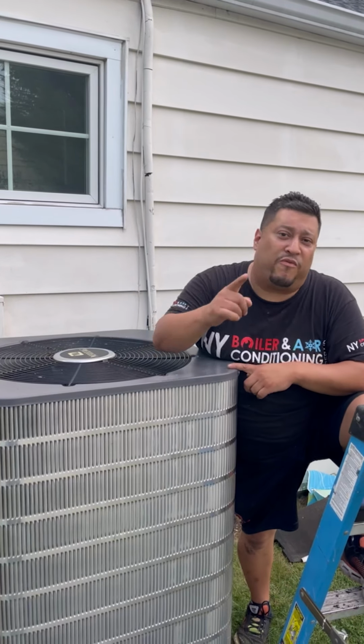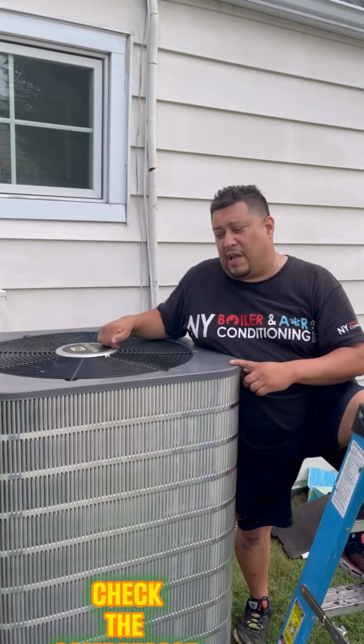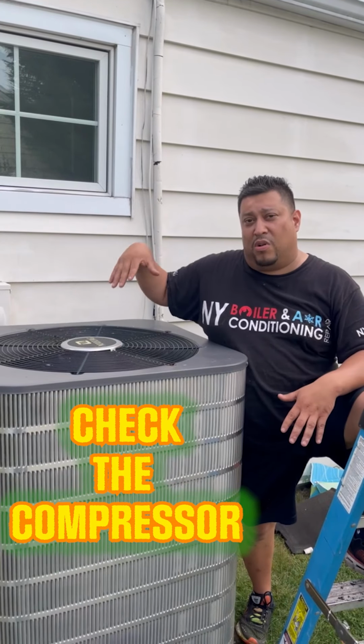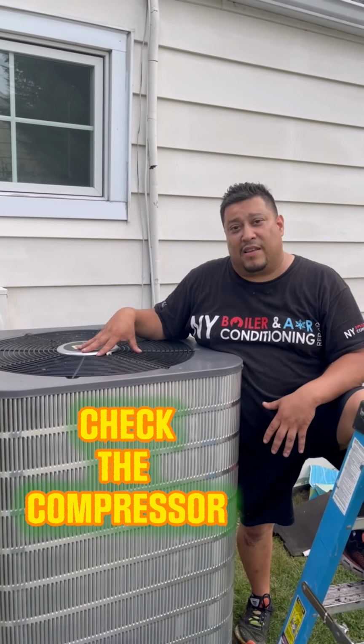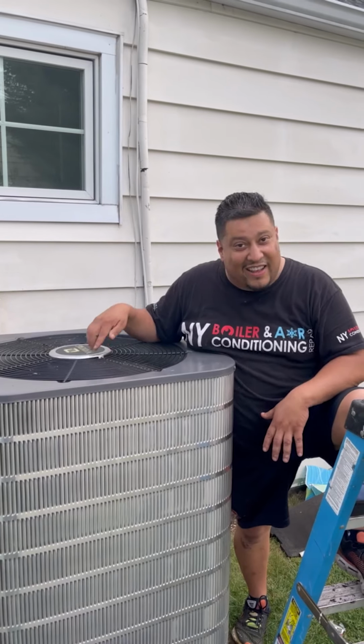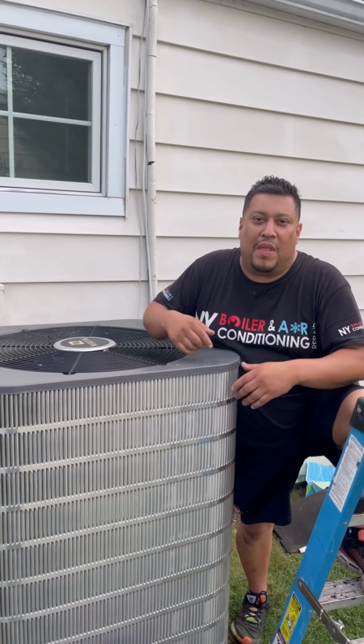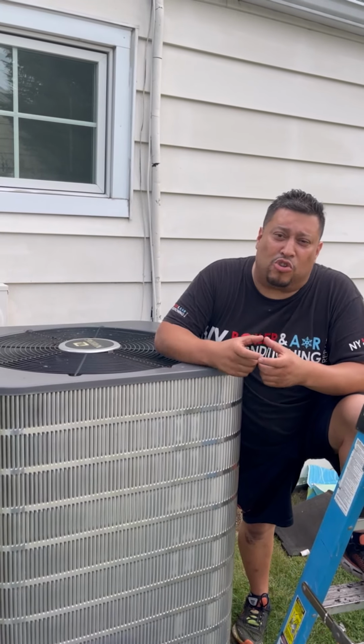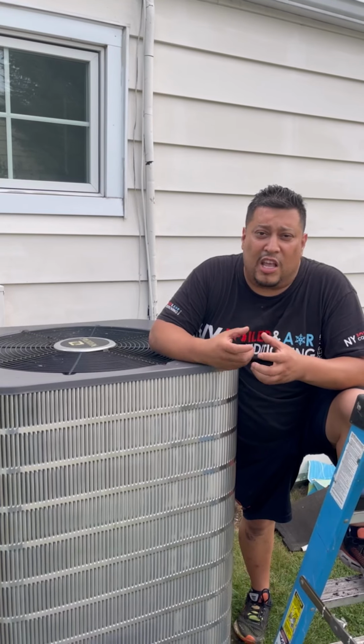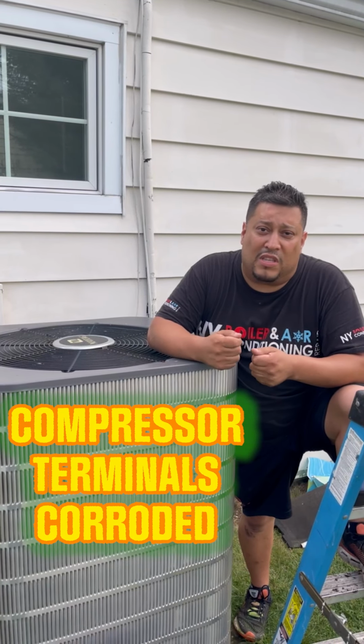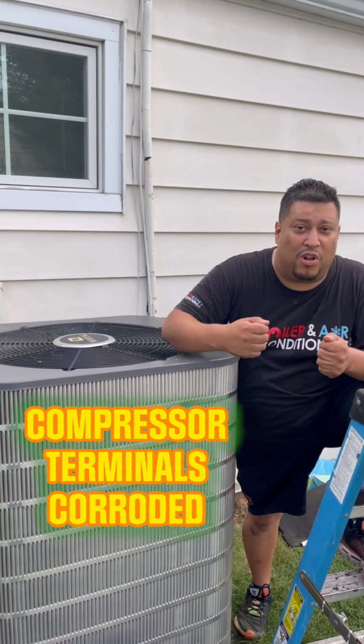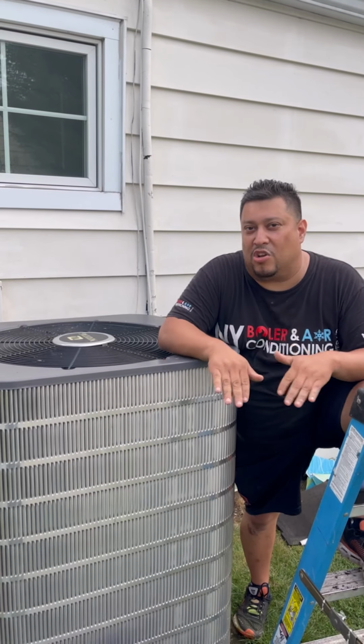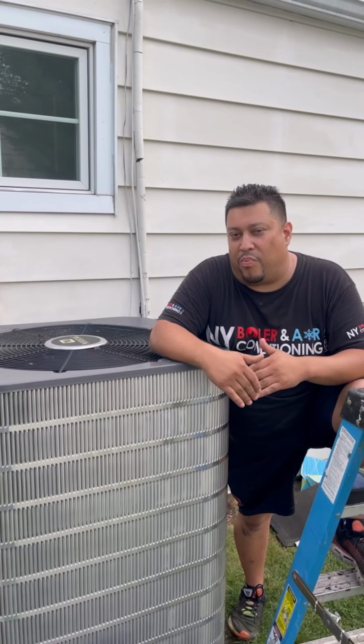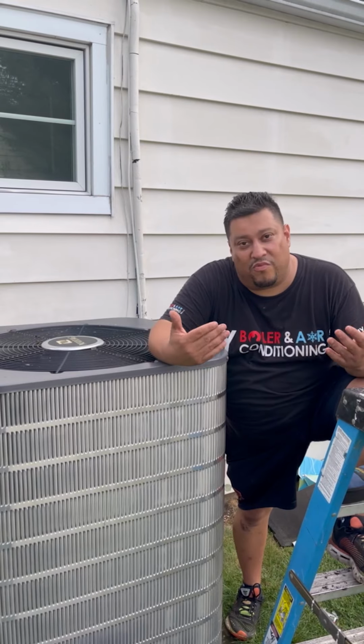But I take it one step further. I go to the compressor. I have to take this cover physically off, and I go inside the actual condenser. Yes, my fat ass fits in there, so I get inside there. So I got inside there, I checked, and I can see that the actual terminal, the common start and run terminals, is corroded. And of course, when you do a test from the chassis to one of the terminals, you're getting a continuity. That tells you right away you have a dead short in the compressor. You cannot fix it, you gotta replace it.